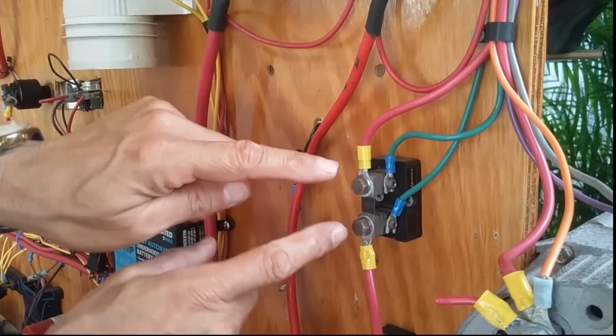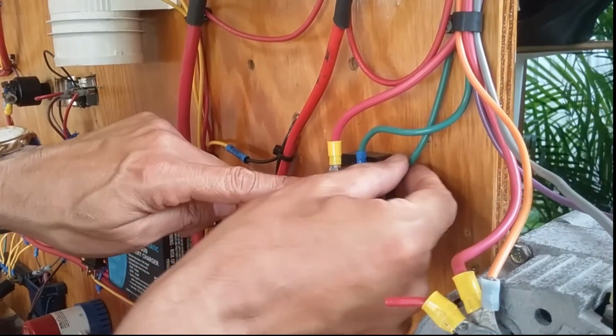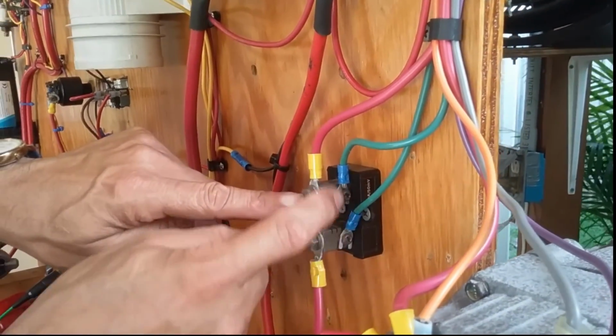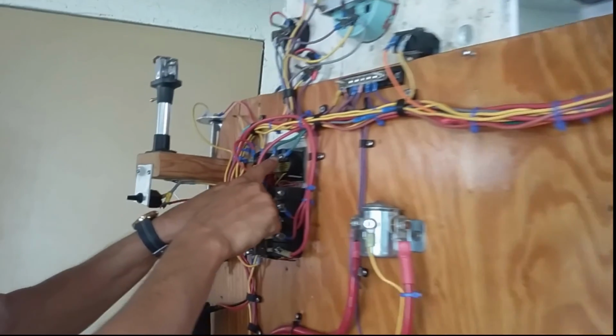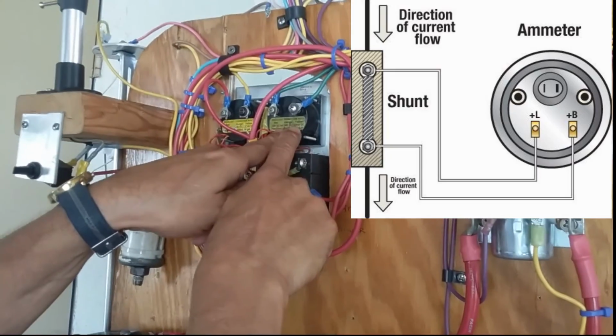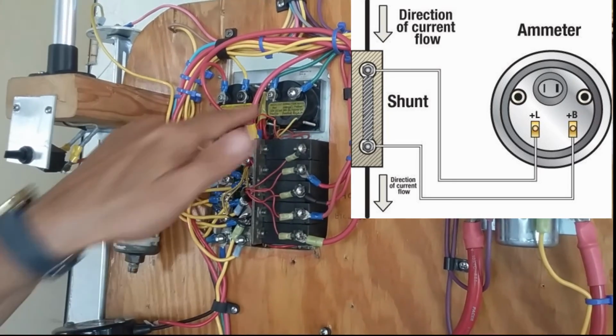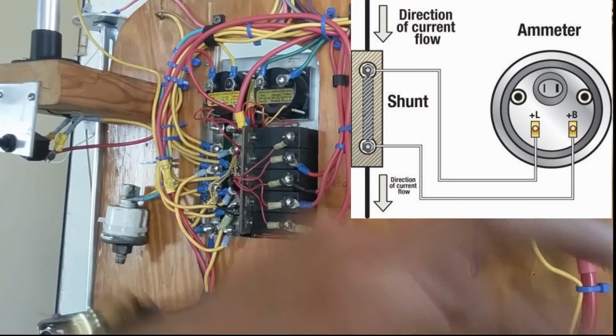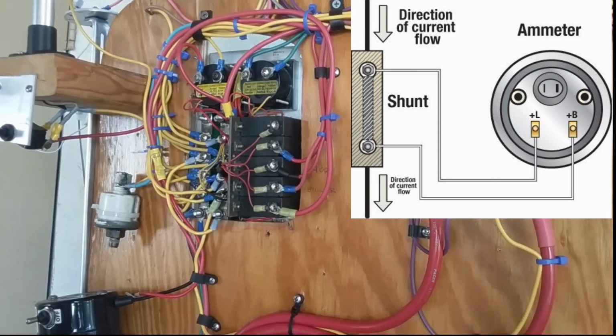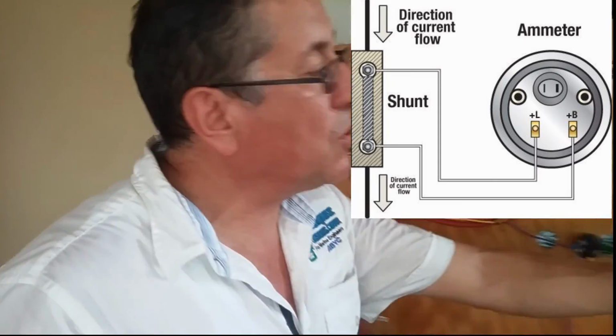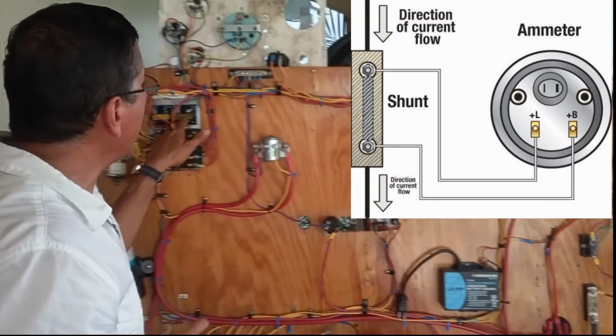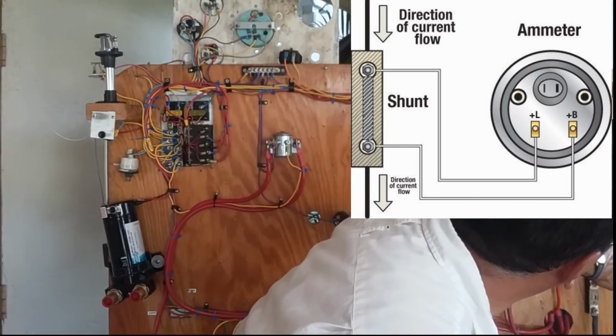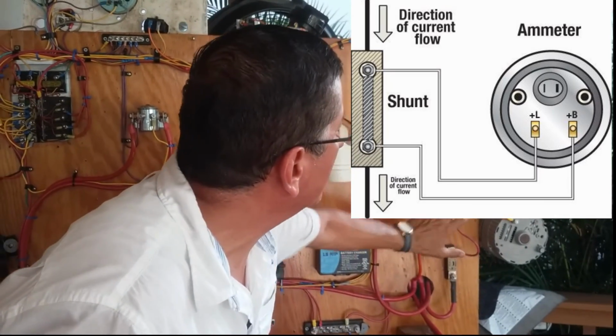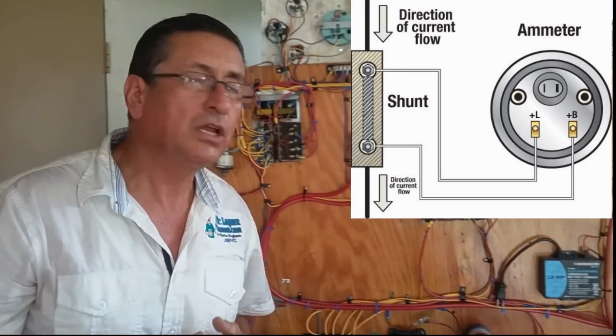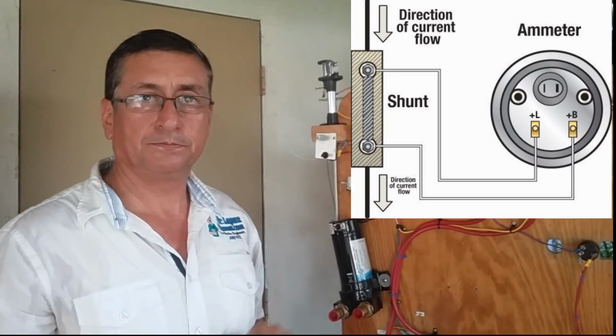On the side of the shunt, there are two small connections where I connect both small green cables, and those small green cables enter here into the ammeter, and this is the connection for the ammeter. And right now the ammeter is connected with those green cables and protected, because the big current does not pass through the ammeter, only the small current that is in parallel with this. The shunt is a protector in order to protect the ammeter.